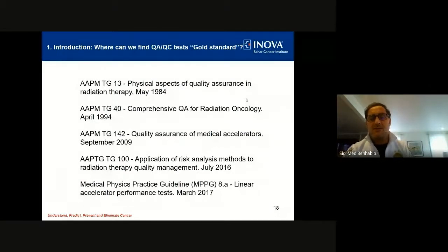So as I mentioned previously, in the US, the AAPM TG reports are considered the gold standard. AAPM stands for American Association of Physicists in Medicine, and TG is task group. One of the earliest task groups about QA was published in 1984, and that was task group 13. And then a decade later, TG 40 was published, comprehensive QA for radiation oncology. We still use it to this day. As you can see, this paper was published in 1994, but we still use it.